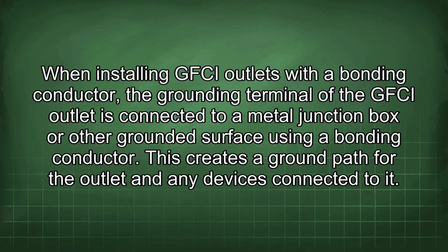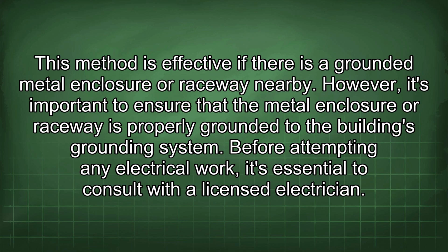When installing GFCI outlets with a bonding conductor, the grounding terminal of the GFCI outlet is connected to a metal junction box or other grounded surface using a bonding conductor. This creates a ground path for the outlet and any devices connected to it. This method is effective if there is a grounded metal enclosure or raceway nearby. However, it's important to ensure that the metal enclosure or raceway is properly grounded to the building's grounding system.